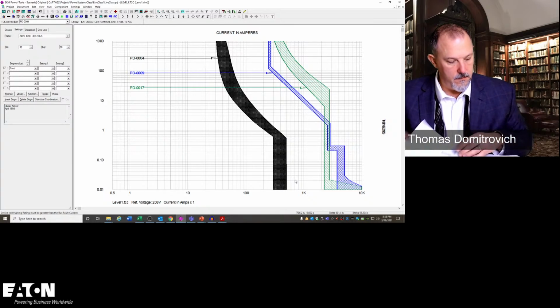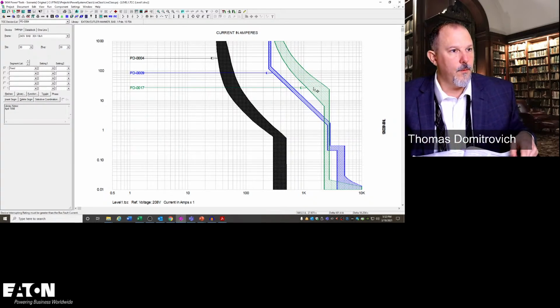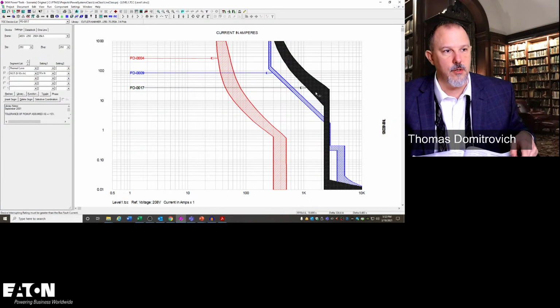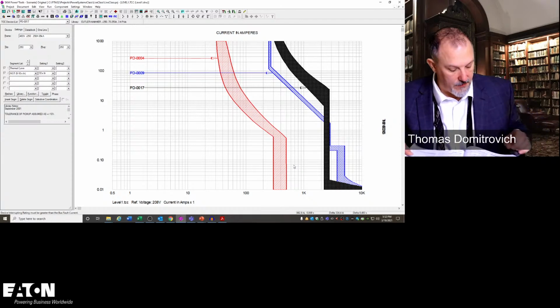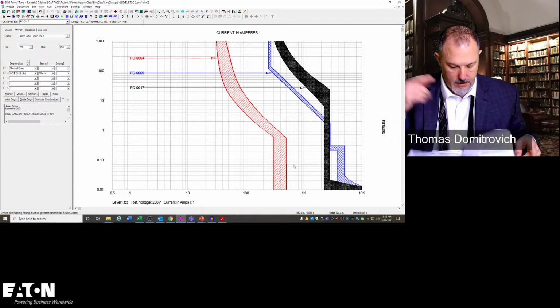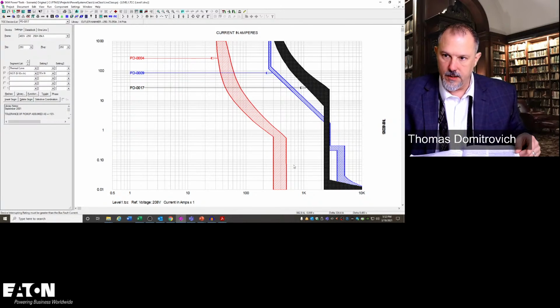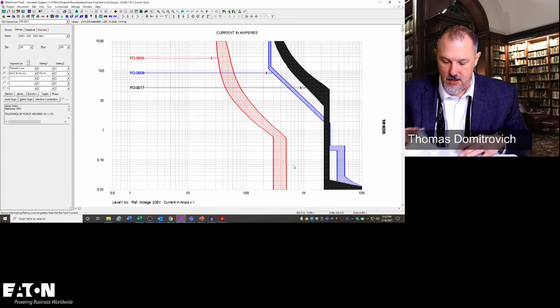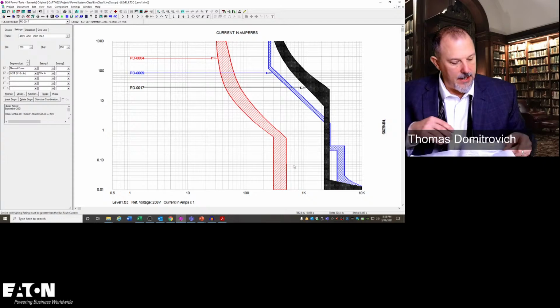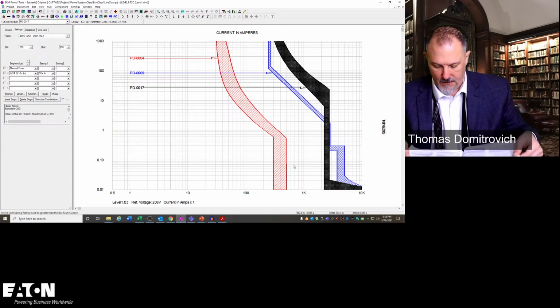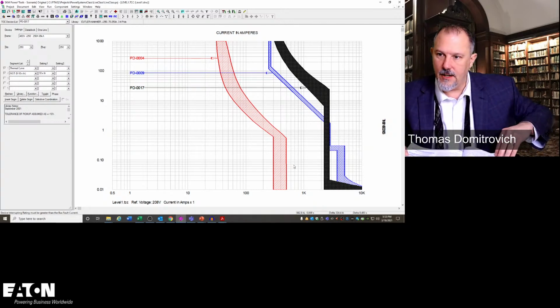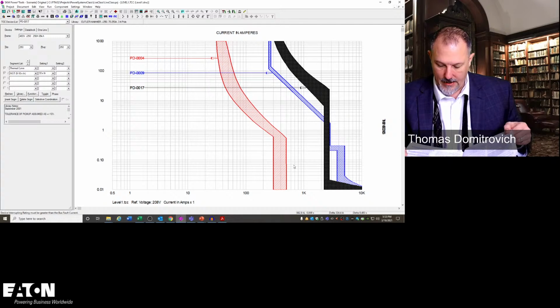While I look for the section, have I achieved, whether I use this one or this one, both of these are the same, so don't ignore this. Between these two breakers and the BAB, do I selectively coordinate? I'm looking for the section while you give me the answers. I got MC says no. MC in the house says no. Is MC right? Is MC wrong? Ryan Jackson, my code guru, the walking code book. For the life of me, I cannot. I'm thinking about those two curves, and I know 517 dot what? 57. Not until you check the table. Okay. Why is that? So MC is saying I have to check the table.